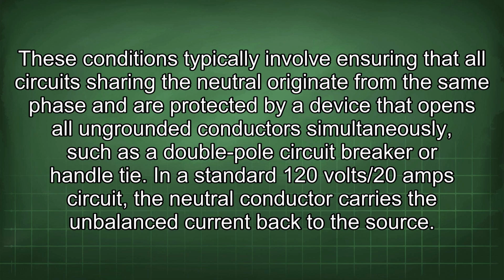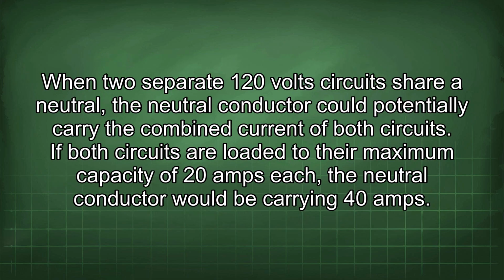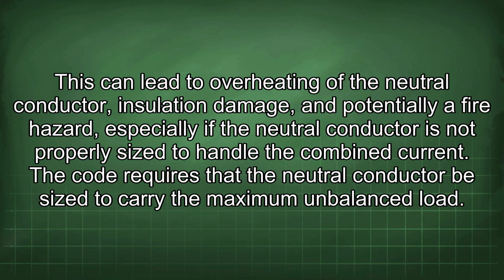In a standard 120 volt, 20 amp circuit, the neutral conductor carries the unbalanced current back to the source. When two separate 120 volt circuits share a neutral, the neutral conductor could potentially carry the combined current of both circuits. If both circuits are loaded to their maximum capacity of 20 amps each, the neutral conductor would be carrying 40 amps. This can lead to overheating of the neutral conductor, insulation damage, and potentially a fire hazard, especially if the neutral conductor is not properly sized to handle the combined current.